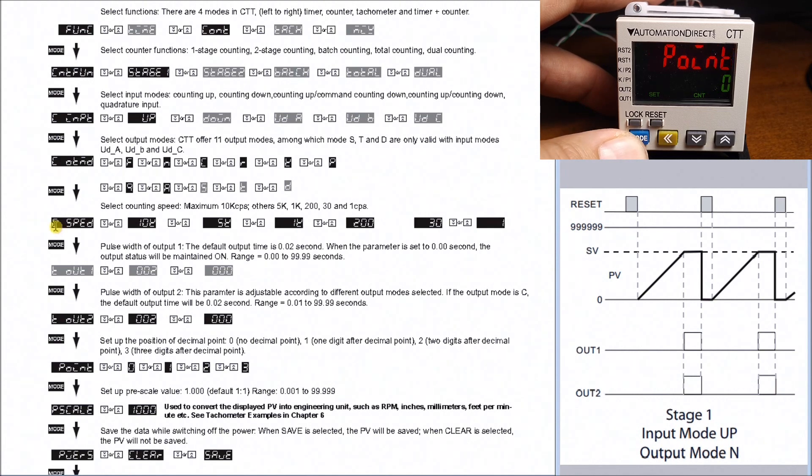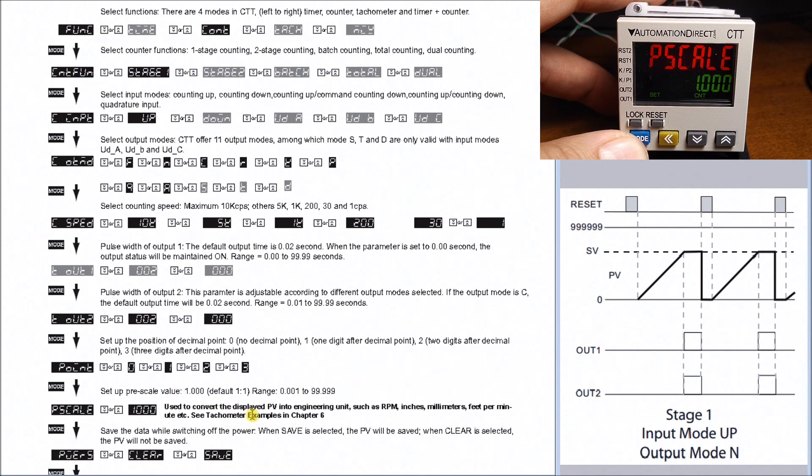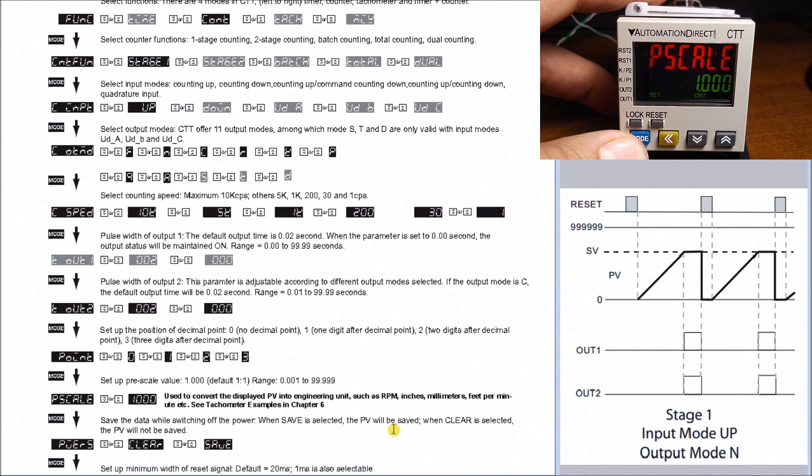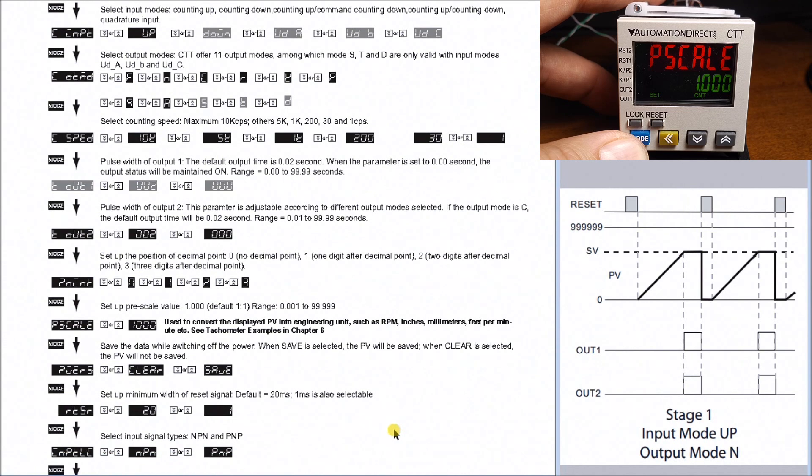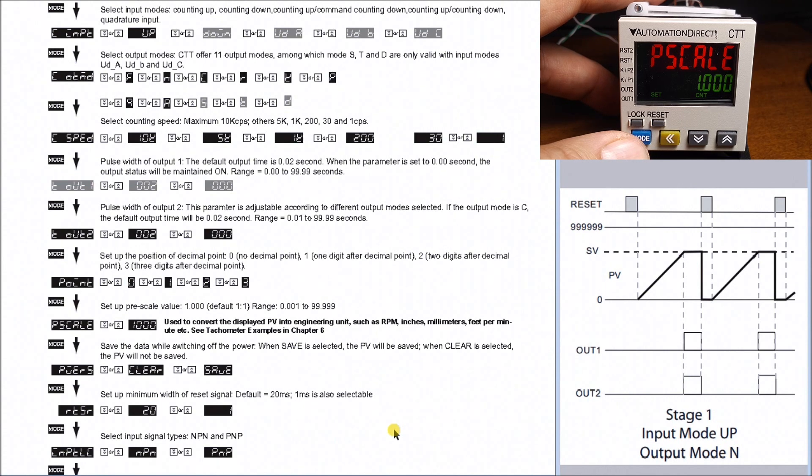Then this is our point or decimal point, and what this allows us to do is change the decimal point number to where we want on that unit. We have our pre-scale, and what that is used to do is to convert into a unit that you want to see displayed on your device. For example, if you're measuring distance, then you want to put in every pulse equals so much distance - you would have this as your pre-scale value that you put in here.